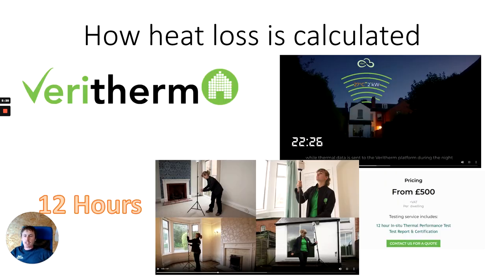Because of the guesswork, you can contract another company — Veritherm, and there are probably a few companies like this coming up especially with all the air source heat pumps. There is a charge; prices are from £500 plus VAT. They'll turn up at your property, ask you to leave for 12 hours, set up sensors in every room with a controlled heat source, and monitor live heat loss data from your property. This takes out all the guesswork about what's in the walls and gives you a live, insured calculation.